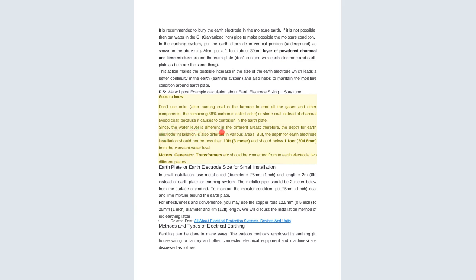Since the water level is different in different areas, the depth of the earth electrode installation is also different in various areas. But the depth of the earth rod installation should not be less than 10 feet, that is 3 meters, and should be below the constant water level. So when we are installing this earth rod, we make sure that we drive it very deep into the ground, not less than 3 meters, that is 10 feet down, so that it can go and meet the earth mass that is down in the ground.